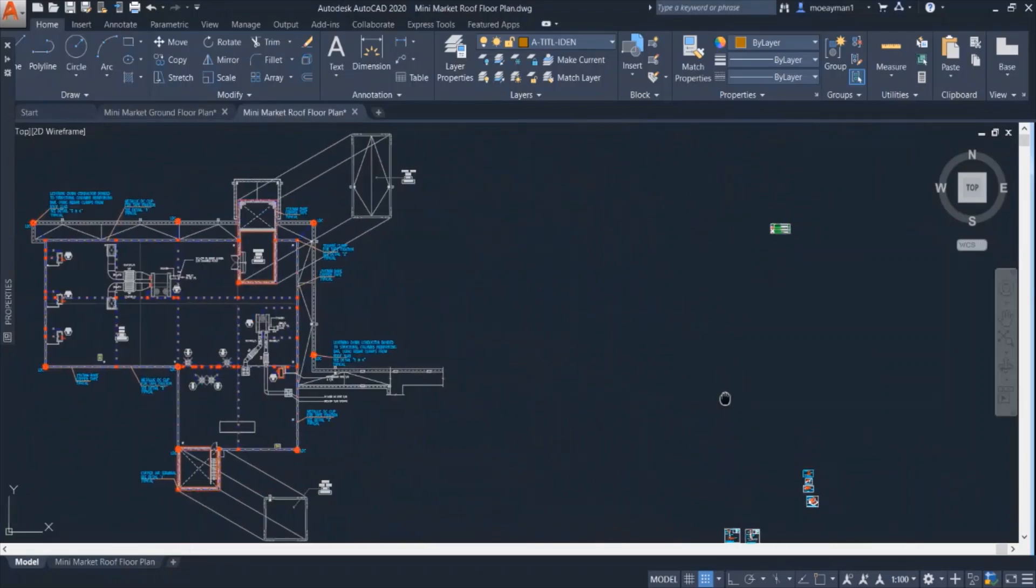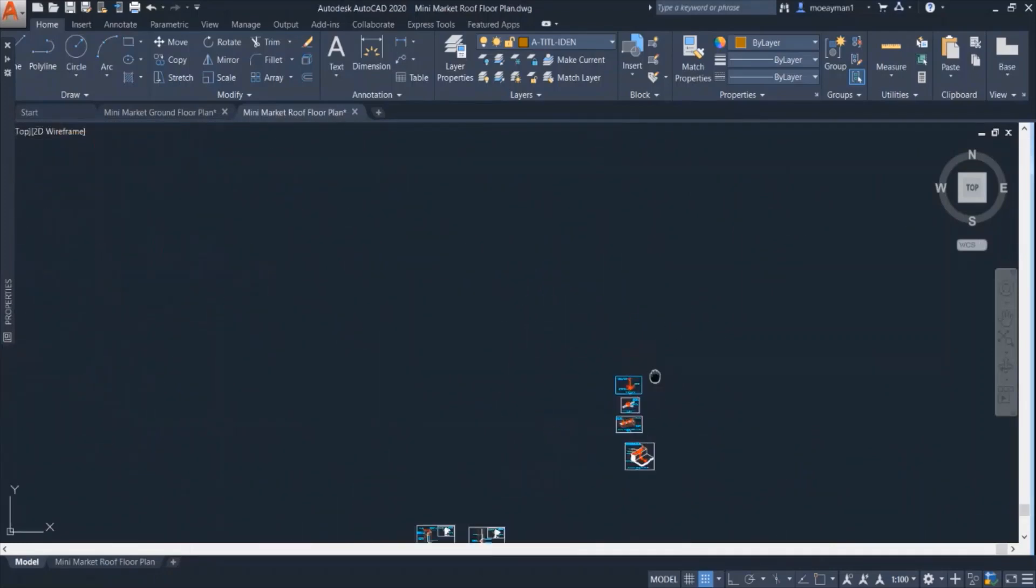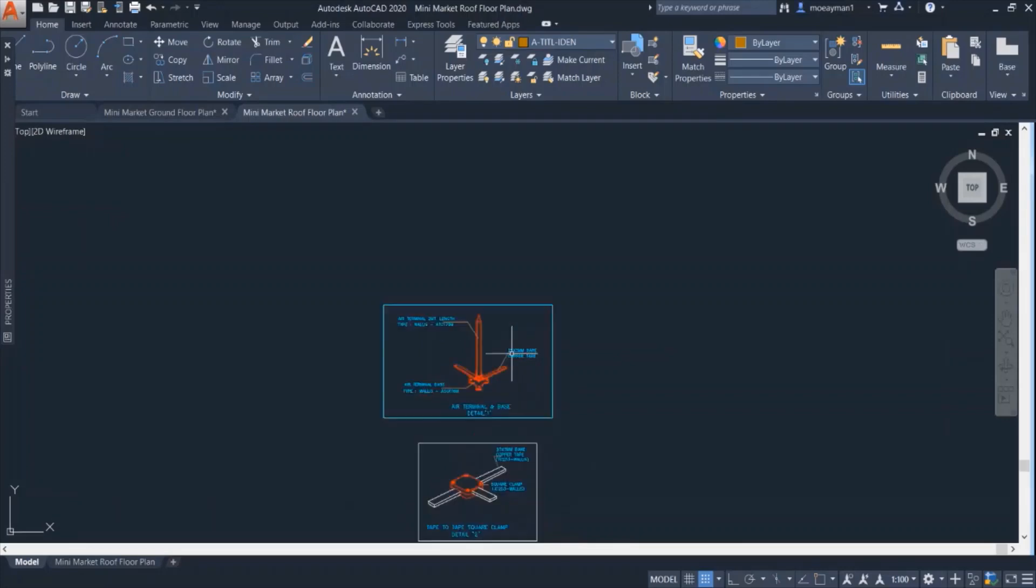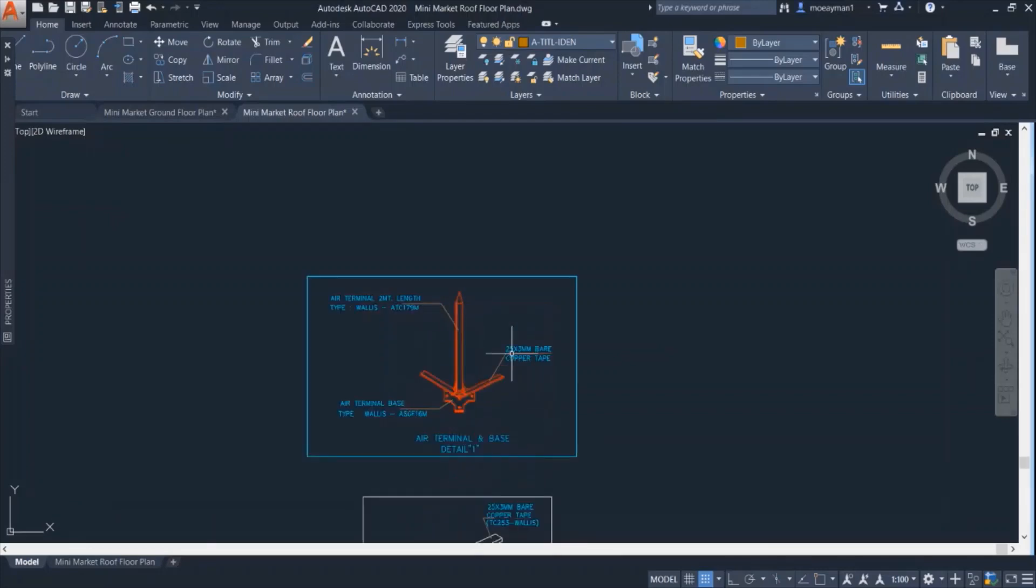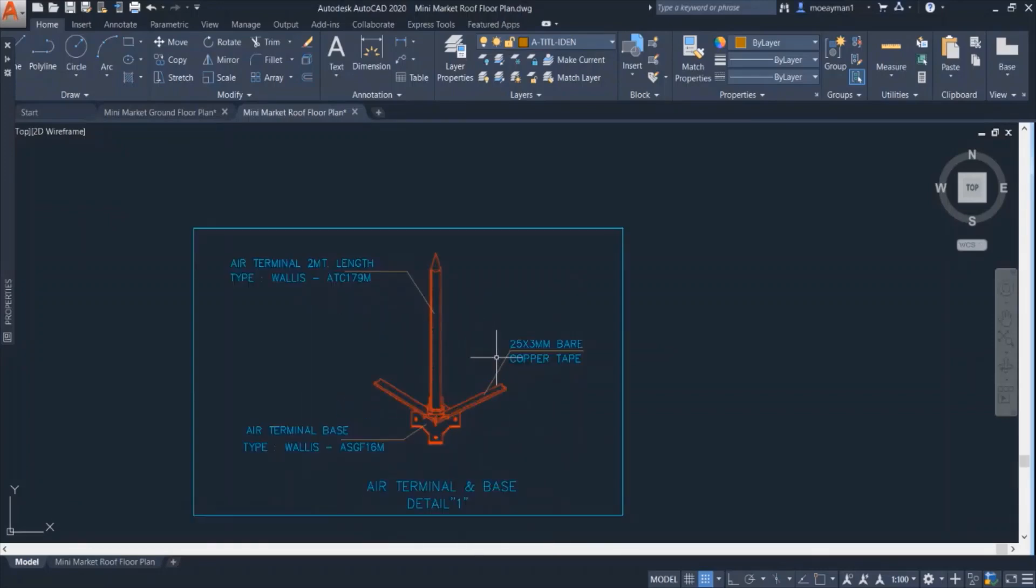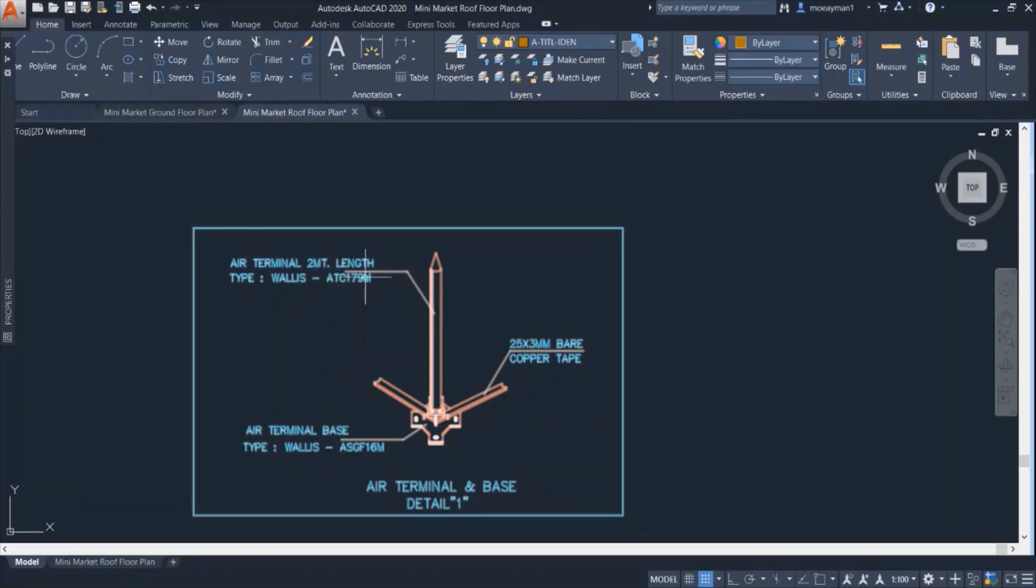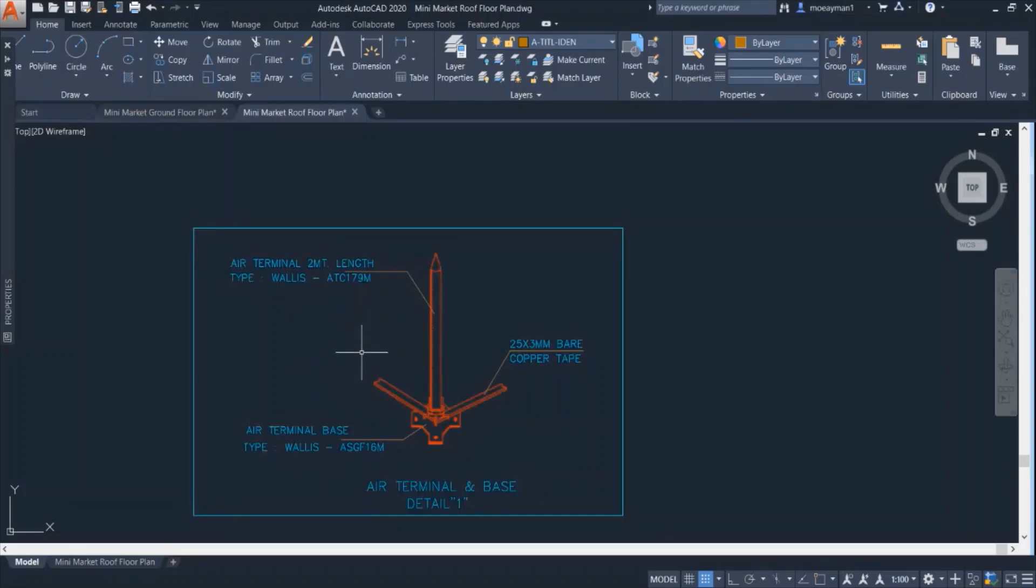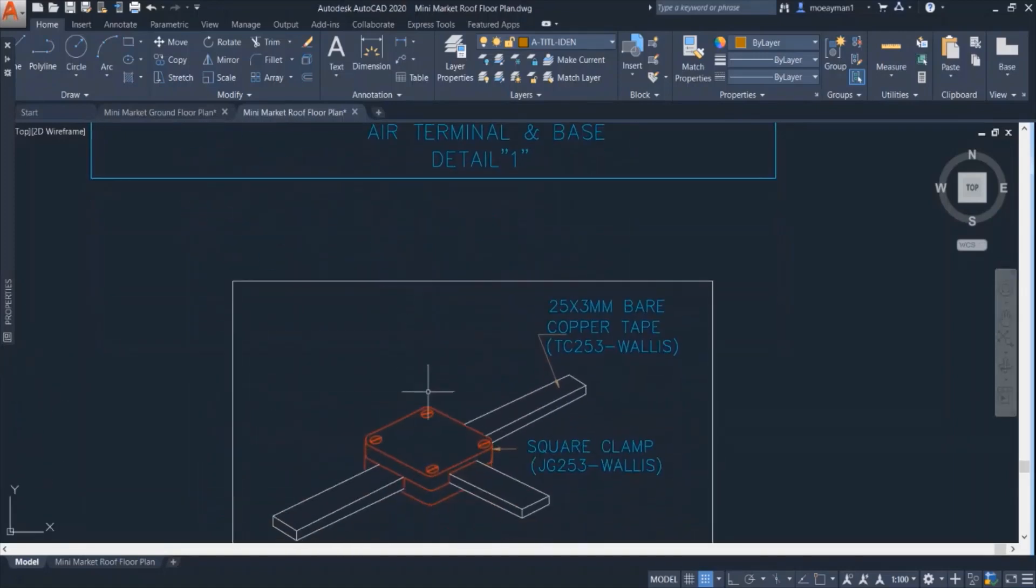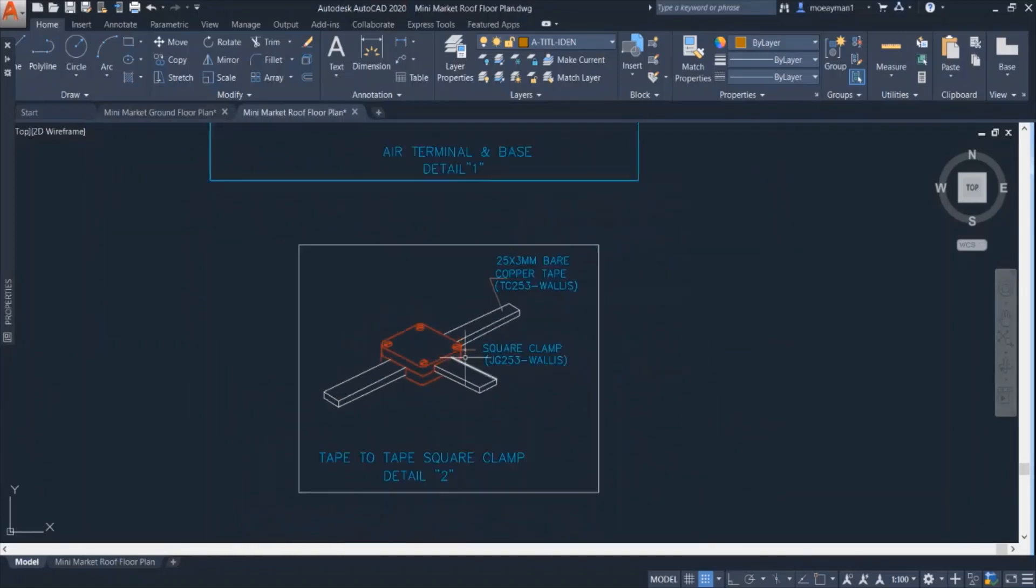Now let's look at the details here to understand more about the components in the roof plan. The first detail here is for the air termination rod. So this is how it looks like for a mesh conductor type. The rod here has a two meters length. Of course you can change the length according to your calculations. Then we have here the copper tape.